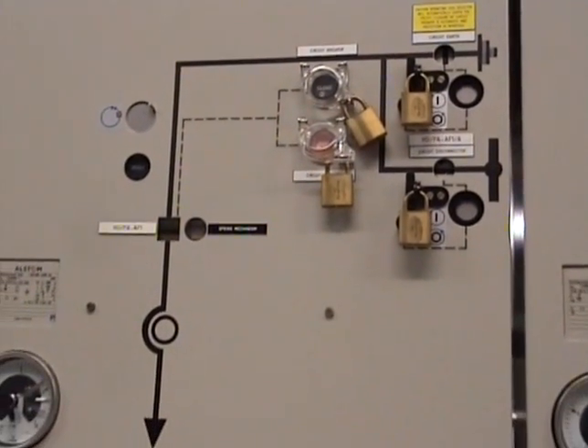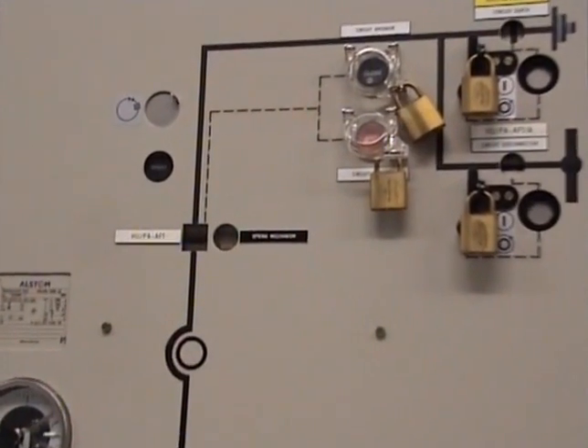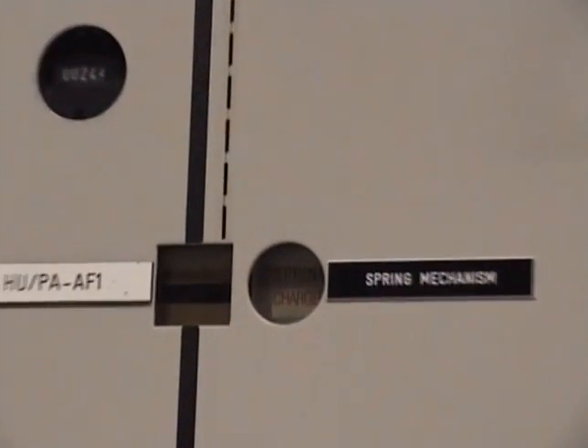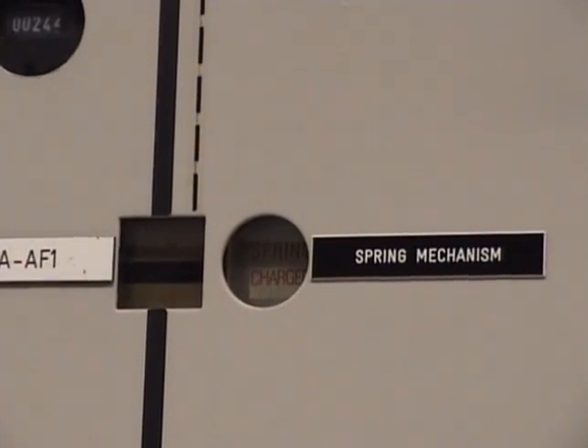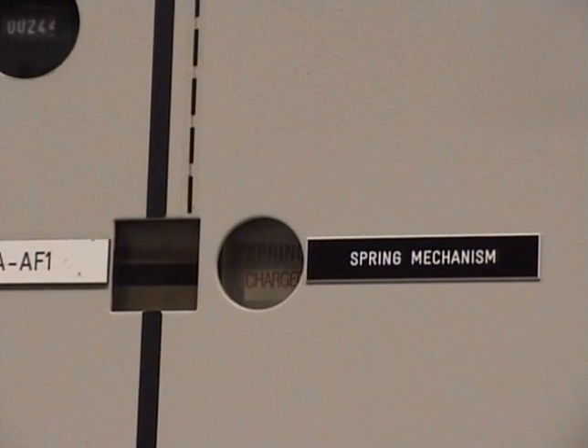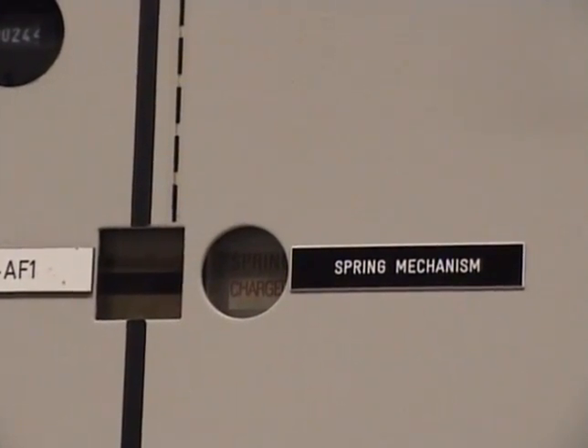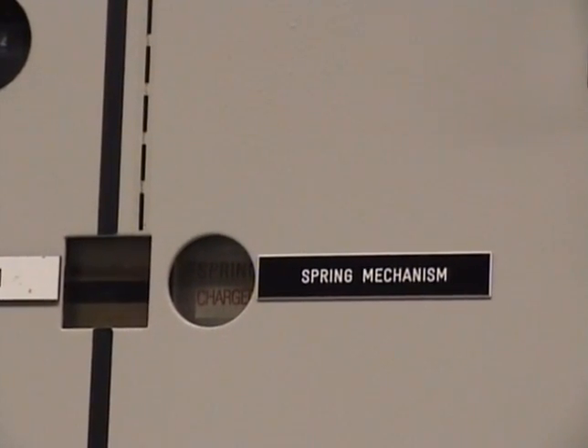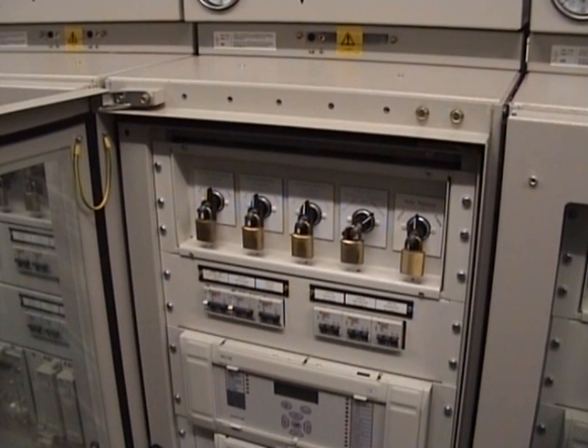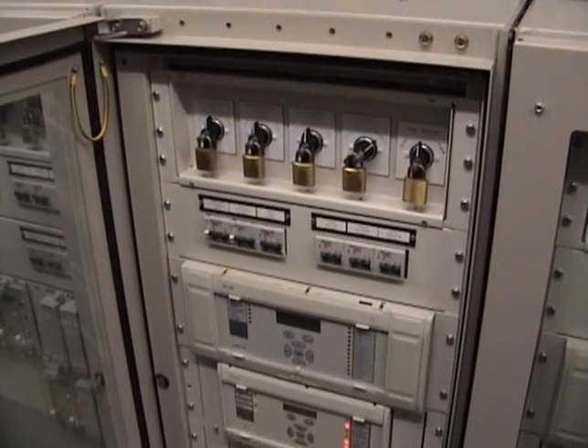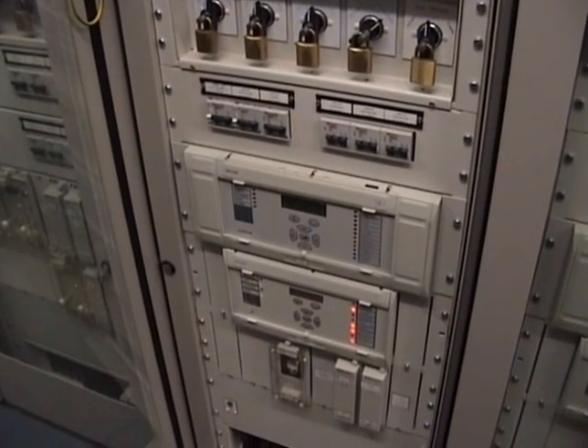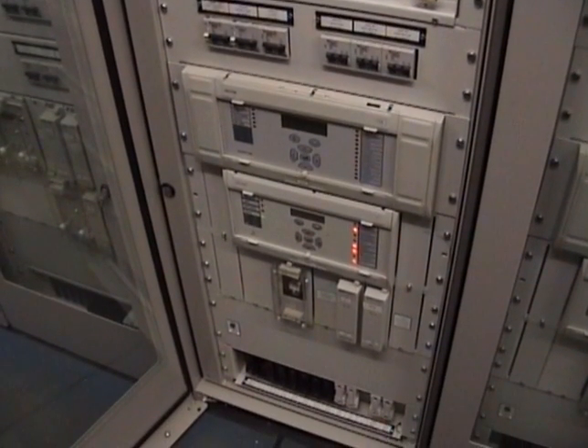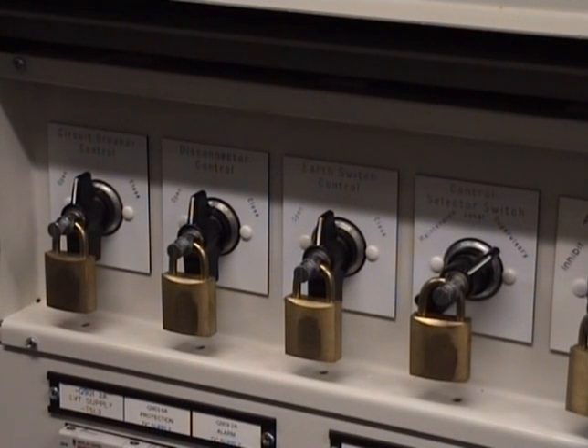Here is the circuit breaker indication, and to the right the spring charge indicator, which shows whether the closing spring is charged or free. The lower panel contains the controls for operating the circuit breaker and disconnector, and below the protection relays which operate to clear faults. Here we see the control switches to operate the circuit breaker, disconnector and earth switch for isolation or switching purposes.